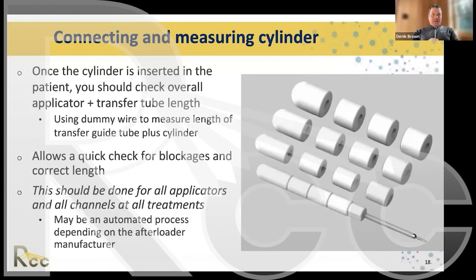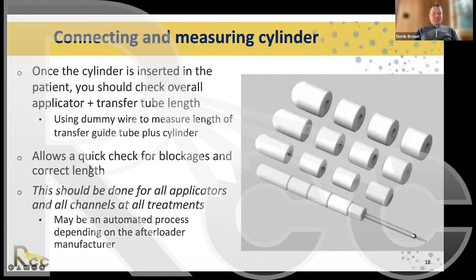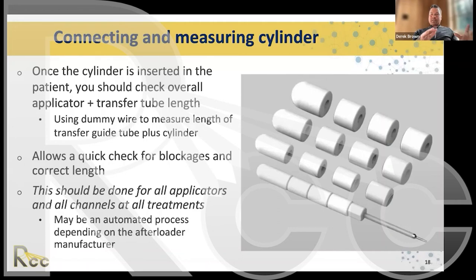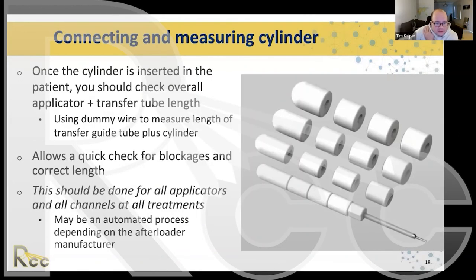After the cylinder is inserted and immobilized, we check that the overall applicator plus transfer tube length is correct using a dummy wire and measurement system. This also checks for blockages and confirms the transfer guide tube is connected appropriately. This must be done for all applicators and all channels before every treatment, ensuring the source will not get stuck and that the length matches what is in the treatment planning system.